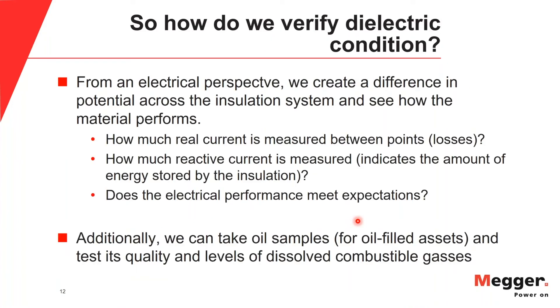How do we verify dielectric conditions? From an electrical testing perspective, we have to create a difference in potential across the insulation system and see how the material performs. All electrical dielectric tests involve applying a voltage and then assessing the material's behavior: how much real current is measured — indicative of the losses occurring in that material — and how much reactive current, indicating energy being stored by the insulation. Does the electrical performance meet our expectations? From an oil approach, we can take oil samples and test for levels of dissolved combustible gases as a means to verify dielectric health.